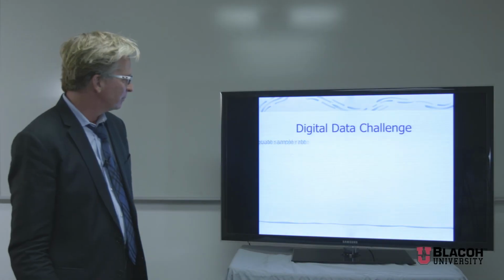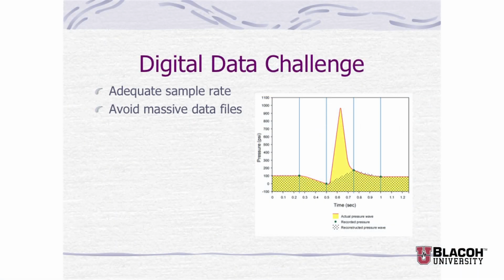Turn off the pump. Goes from 70 psi to 0. Well, the gauge only went to 0, right? And it stays there for a couple seconds and then comes back up at like 160 psi. And the operator's like, so you're not going to tell anybody about that, are you? I'm like, so sorry. The challenge: it's the sample rate, massive data files, and what actually happened.